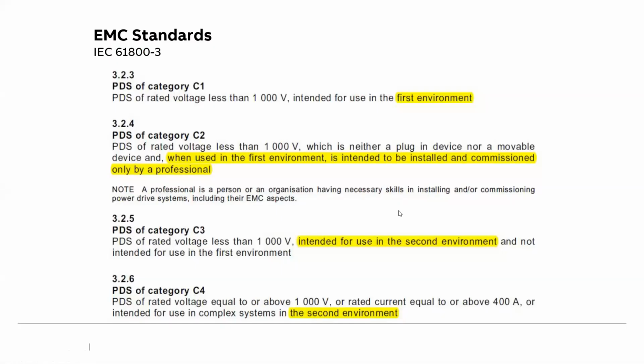So we saw the first and second environment. First environment is basically any premises or building which is connected directly to a low voltage network. And second environment is any premises which has an intermediate transformer inbuilt and is not directly connected to a public low voltage network. Now, within the first and second environment, various categories of EMC filters have been defined. So there are C1, C2, C3, and C4 categories of EMC filters. C1 and C2 are recommended for the first environment, and for second environment, we have C3 and C4 categories of EMC filters.